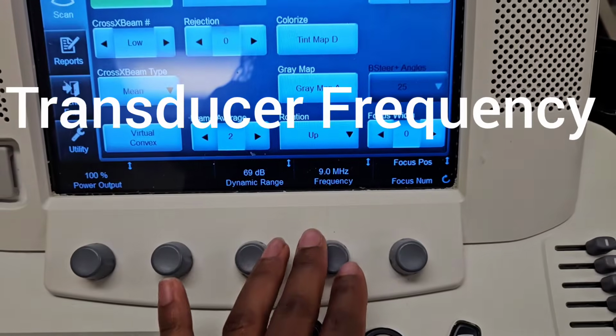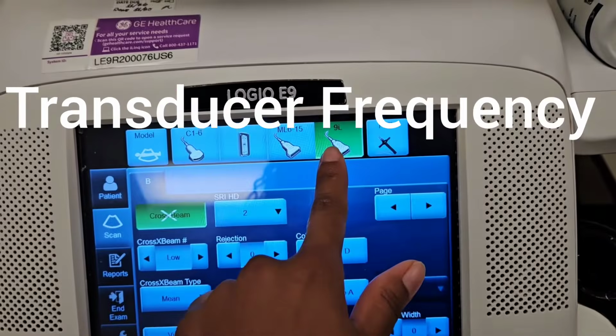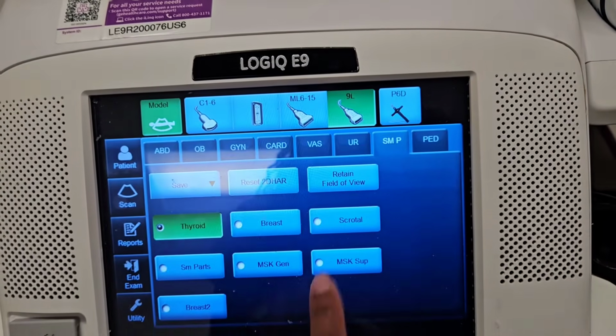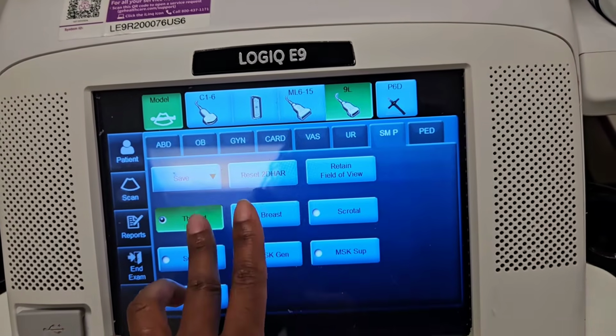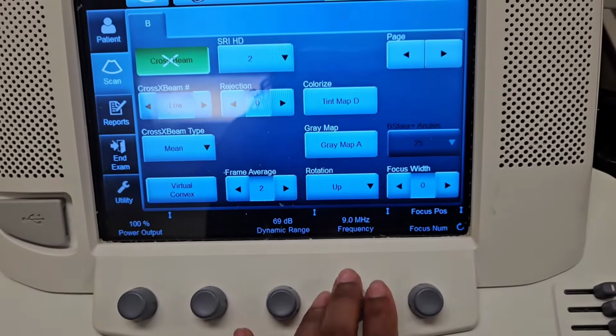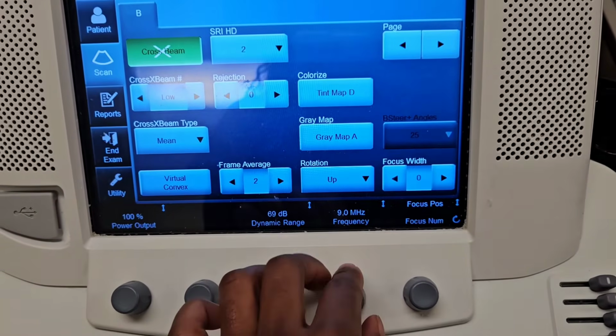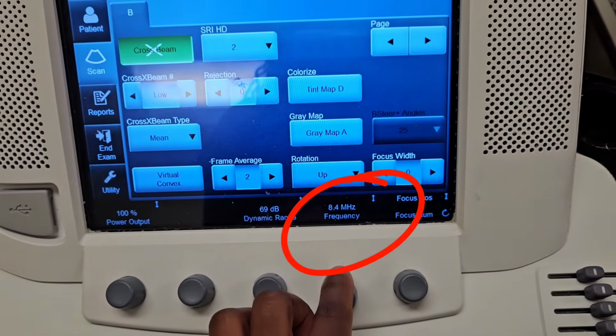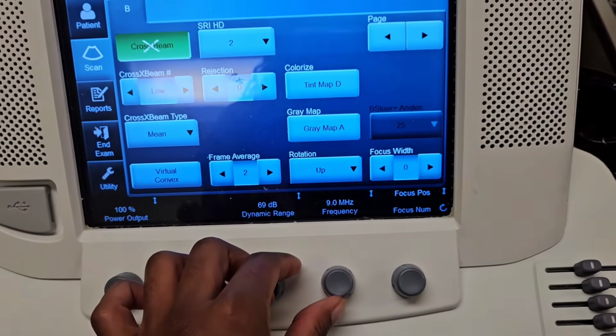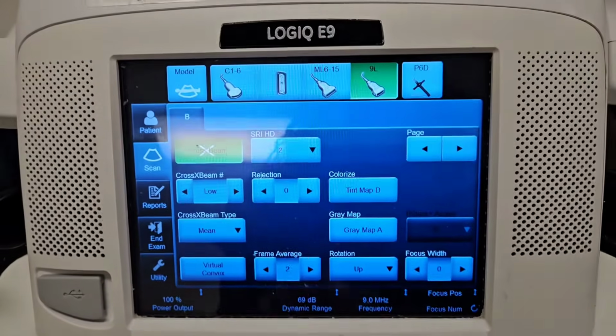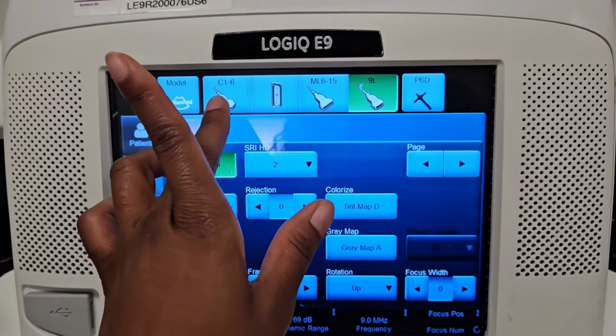Next, we're going to go over the bandwidth of different transducers. You might have, for example, the 9 megahertz transducer. That's not the only frequency that transducer can operate at. As you can see here, this one also has 8.4 megahertz. So if you want to image something slightly deeper, then you can lower the frequency.